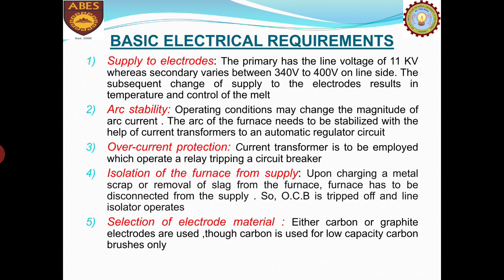Now here comes a very important topic: what are the basic electrical requirements of an arc furnace. What things do we have to take care of while maintaining and creating an arc furnace, or during heating, what things we have to keep in mind. So the first one we have to keep in mind is the supply to the electrodes. Now the electrodes have to be short circuited momentarily and then separated from the charge inside the furnace, which requires a low voltage on the secondary and a high reactance transformer winding.